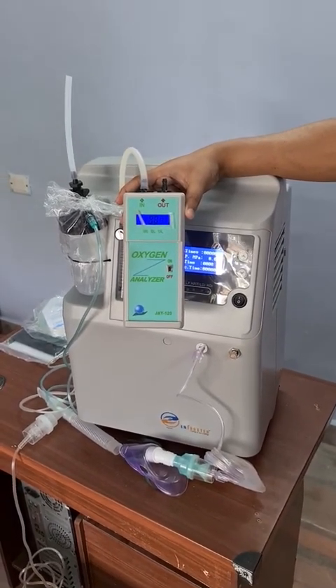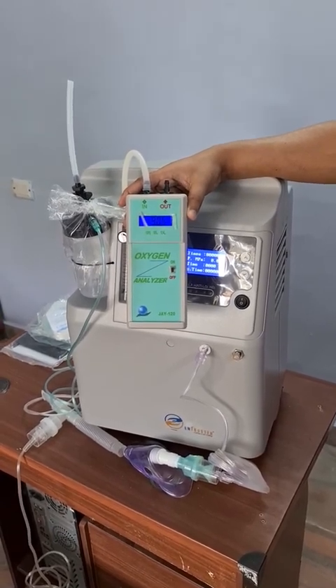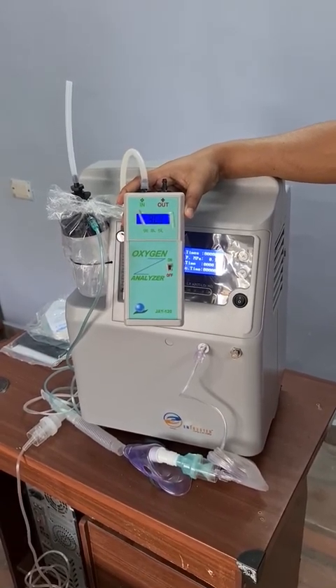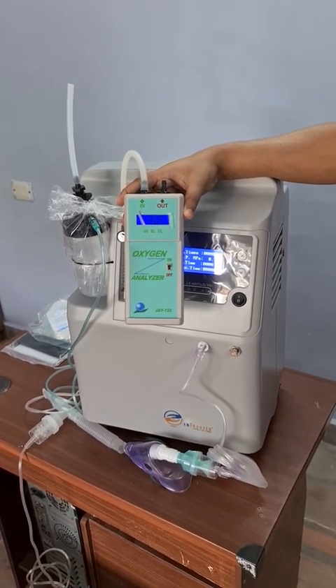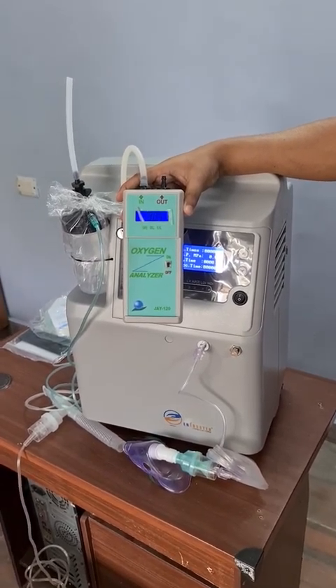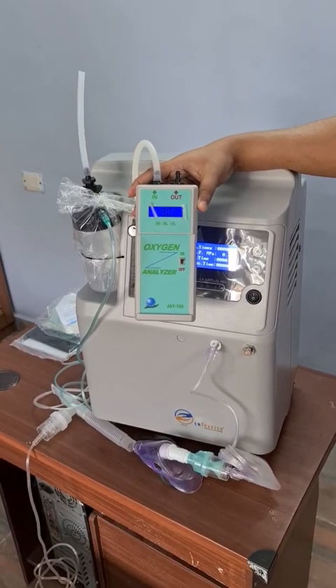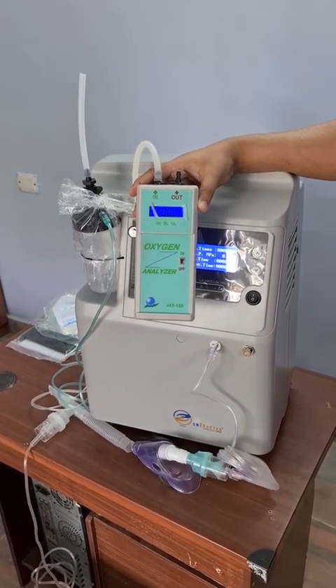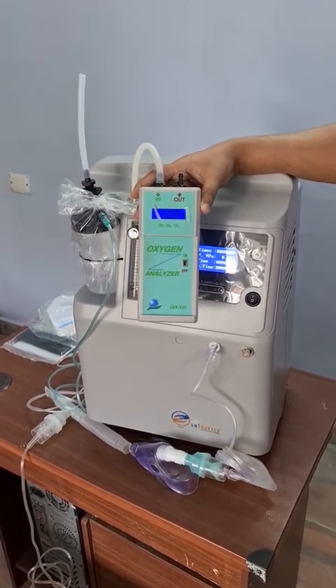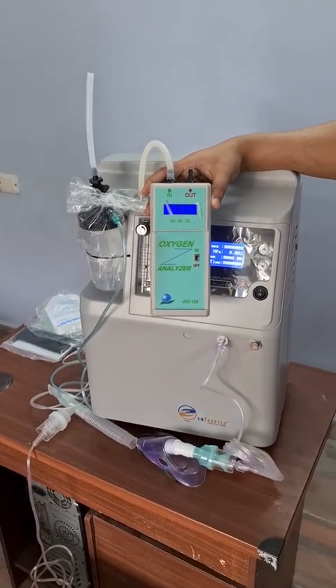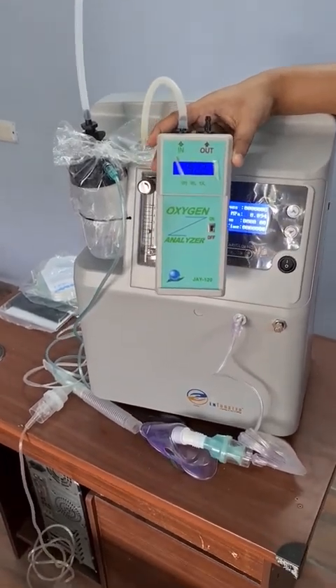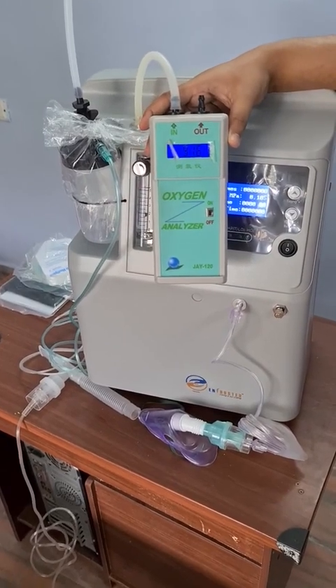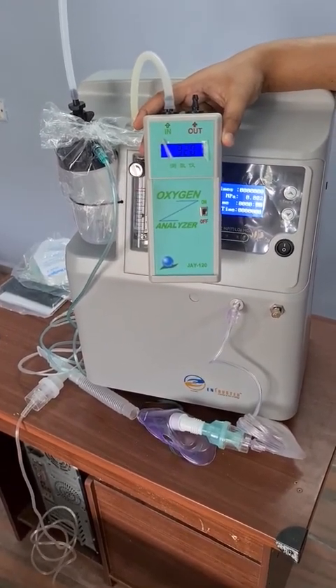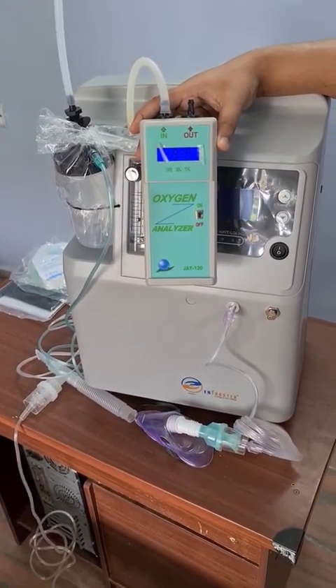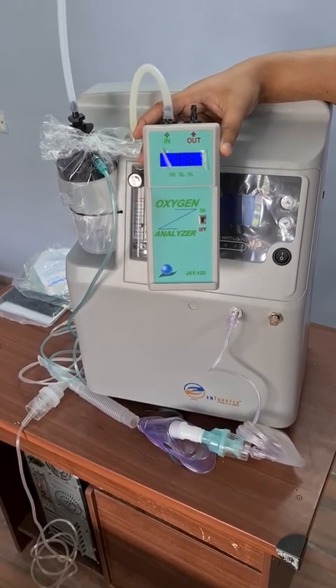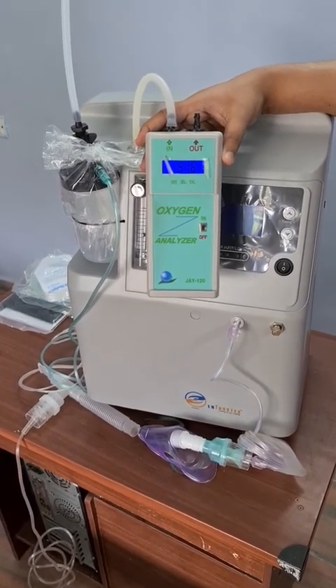You can see with each flushing sound, the concentration is increasing because at that point the nitrogen is getting flushed out. And after n number of cycles, the oxygen will automatically stabilize at its purity. And as per our guaranteed level, it has already crossed. We are giving a guarantee of 93% plus or minus 3. So you can already see the concentrator has reached a purity level of 92%. Anyways, let us wait and see the maximum it reaches.